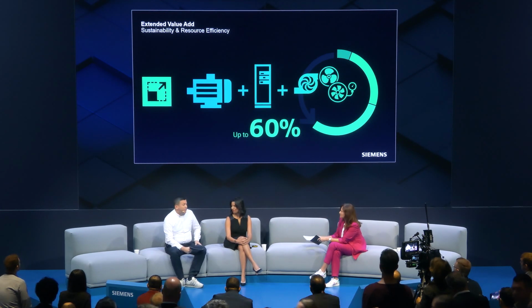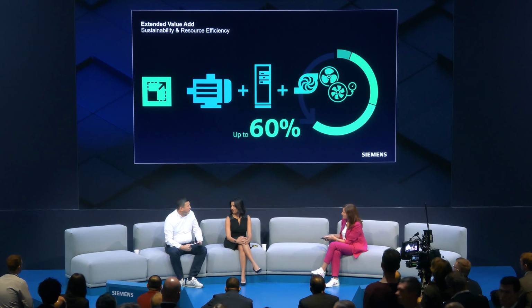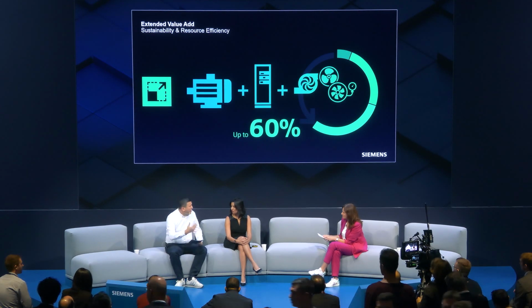Of course. Based on the data we collected from the site, we also analyzed the energy consumption perspective, because we can see all the energy consumption. So we made an analysis and then submitted it to the customer, showing that there is a huge potential they can implement there. With our new efficiency electrical motors, we suggested they replace 51 motors, and the Hayat management accepted to change the 51 motors based on our proposal.